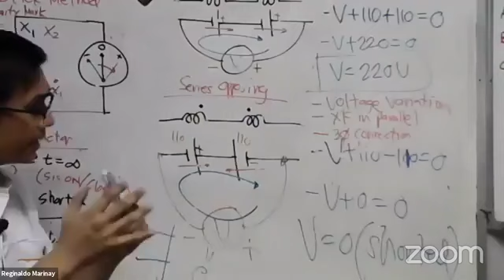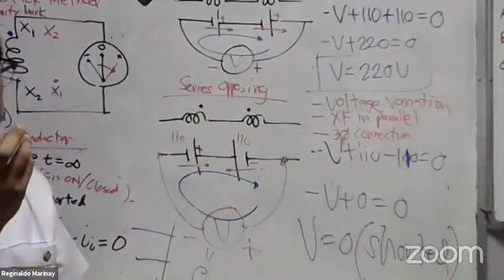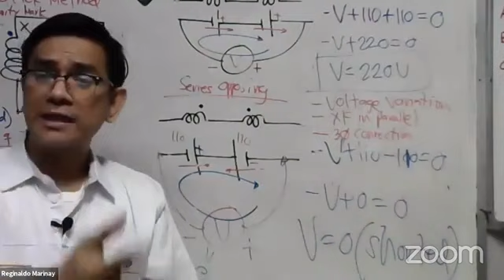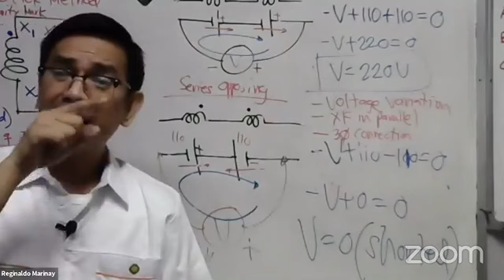Even when you connect a transformer in parallel, you should connect H1 to H1 of the other transformer, H2 to H2 of the other transformer on the primary side, let's say. On the secondary side, if you want to parallel two transformers, you have to connect X1 of transformer 1 to X1 of transformer 2, not X2, not X2 — that may be shorted. Well, it depends on the voltage distribution of the coil.